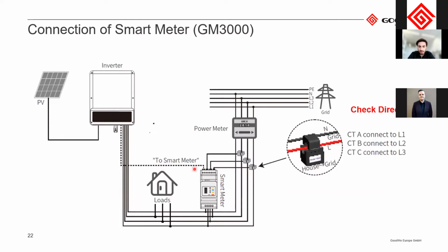With the smart meters, this is the RJ45 cable that goes to the inverter. Otherwise, here on the top for a 3-phase inverter, you will have 3 CTs. The CTs are then clamped on just before the grid connection point. So if you have a power meter, usually in the facility, you just attach the CTs before that.